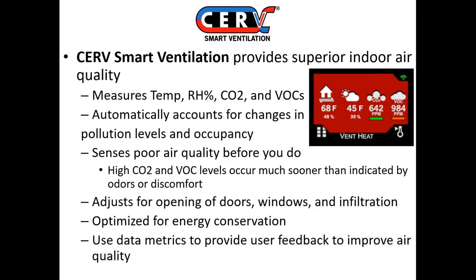Smart ventilation specifically that we reference the CERV with, it measures temperature, humidity, CO2 and VOCs. These are on the indoor side. And then it automatically accounts for changes in pollutant levels and occupancy or activities within the space to ensure good air quality at all times. The system senses poor air quality before the occupants do, or it should, as you can have impacts on health and cognition at levels well before human detection. It also automatically accounts for infiltration or opening doors and windows or other things that will impact the air quality. And then it's optimized for energy conservation.